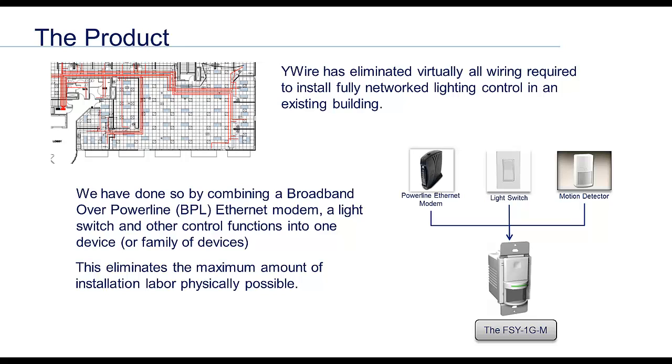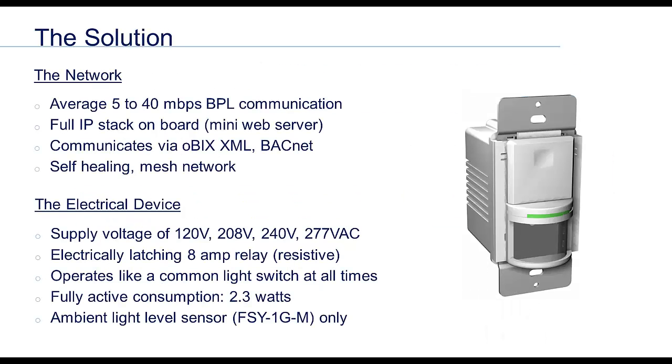This means we can install fully networked lighting control in an existing building without pulling a single wire. The YWire devices communicate very quickly — in fact at fiber optic speeds — over existing commercial and industrial power lines. The communication protocol on the device level is Obix XML. This network seamlessly migrates directly into the JACE by Tridium and virtually any of its resellers' JACEs. YWire also offers a fully graphical BACnet interface for integration of the 5 series lighting control system into almost any native BACnet building automation system.